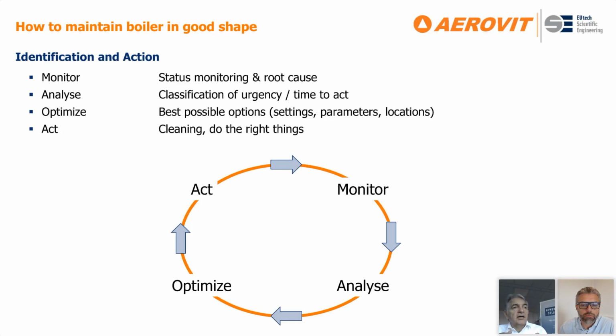a regular basis, you might end up with thermal shock, with high maintenance costs, because you have to exchange heat exchanger pipes. If you do it too late, you might insulate the surface by freezing the deposit on it, and it decreases the heat efficiency, the transfer of the heat to the pipes, and you shift your whole thermal balance towards the economizer, which ends up in poor steam quality and low efficiency. So doing the right thing at the right time is very essential.